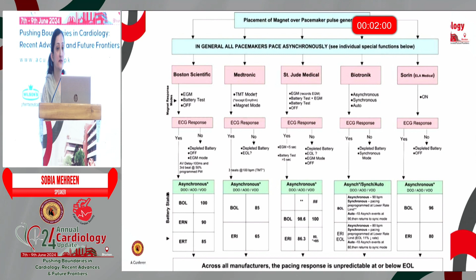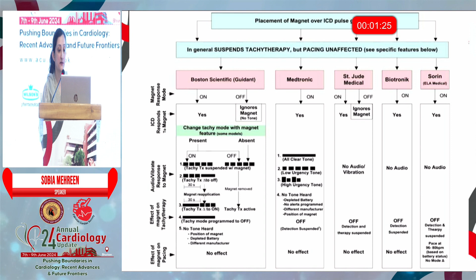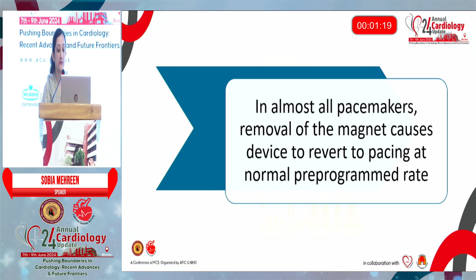There will be beeping sounds when the magnet is placed. And some of the devices need to be turned on the magnet function before the magnet effect can take place. For example, in Boston Scientific and St. Jude's devices, we need to switch the pacemaker to on position before the magnet response can occur. The other devices do not need them to be turned on for the magnet response to occur. Once the magnet is removed, the device reverts back to the pre-programmed rate.